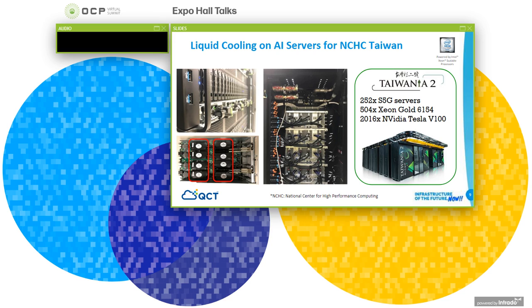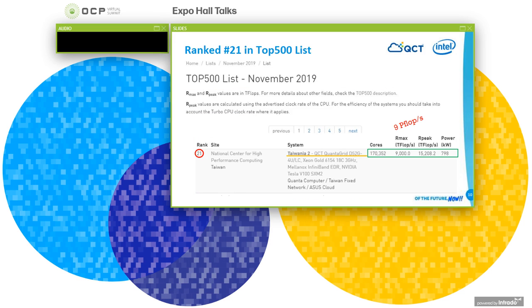The heat dissipation required for this supercomputer is enormous, such that traditional air cooling may not be able to handle it. QCT adopted an innovative liquid cooling technology on this supercomputer. The whole system is kept cool to maintain efficient operation by coolant injected from a tank located on top of the rack.